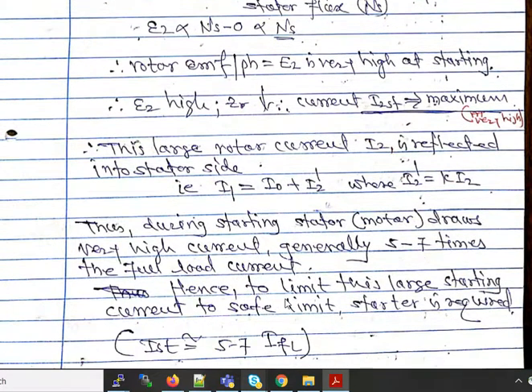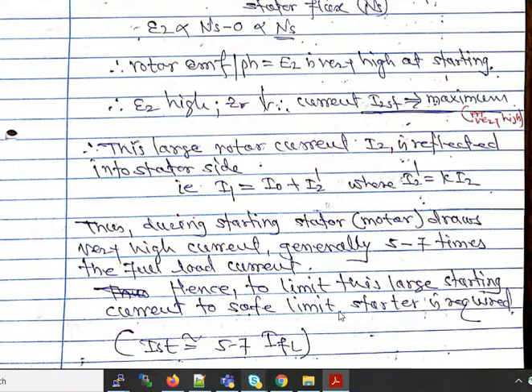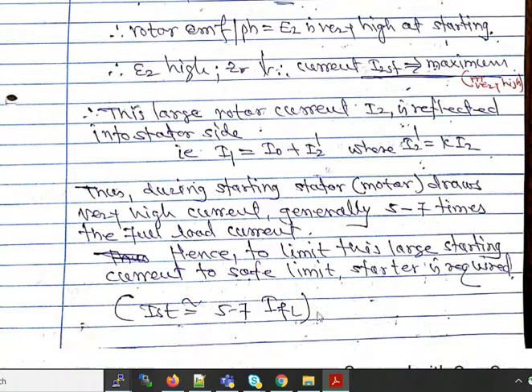This large rotor current i2 gets reflected into the stator side, where i1 = i0 + i2', with i2' = k·i2. Thus during starting, the motor draws a very high starting current — generally 5 to 7 times the full load current — and hence a starter is required to limit this heavy starting current to a safe value.